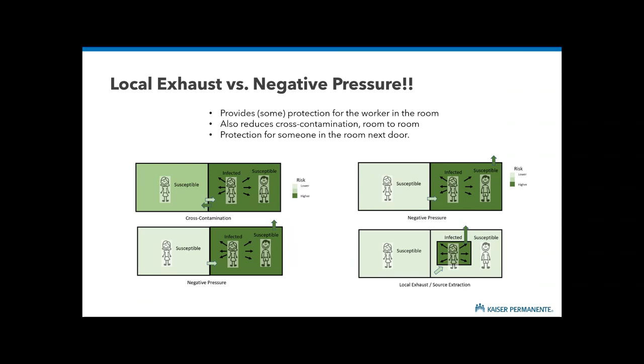All of the other negative pressure schemes provide zero protection for the healthcare worker in the room. They only protect the guy in the hallway. This arrangement is designed to capture potential aerosols at the source and then remove them. So it protects the guy in the hallway, but it's also removing contaminants from the space with a little bit of directionality. So there's some chance that it is actually providing protection to the folks in the room.